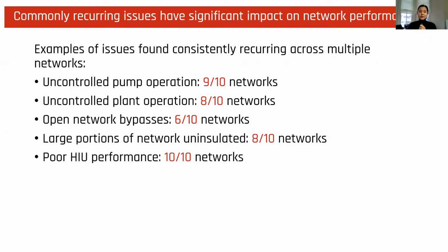We could see 6 out of 10 networks had open network bypasses, which drives return temperatures, heat losses, and pump electricity consumption. We could see that 8 out of 10 had large portions of uninsulated pipework on the network, which drives heat loss. And all 10 networks investigated had instances of poorly performing HIUs. And if you remember from the last slide, these are all items which can be rectified at a relatively low cost.